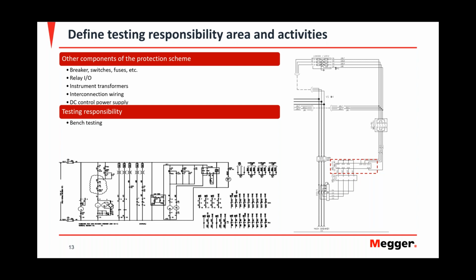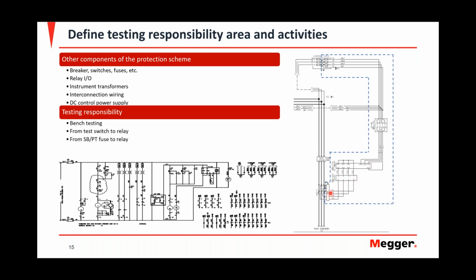Am I only testing the relay? In that case, am I only doing a bench test? Or am I testing something that's installed? And am I testing from the test switch into the relay, which is one of the easiest ways, having a test switch installed, and then you test from this test switch into the relay? Or you could test from the shorting block on your currents, and the secondaries, or from the secondary of your PTs, from the fuses all the way down. In that case, you're testing all the secondary wiring from the secondary of the PTs all the way down to the relay. So what you're responsible for and what you're checking becomes bigger.